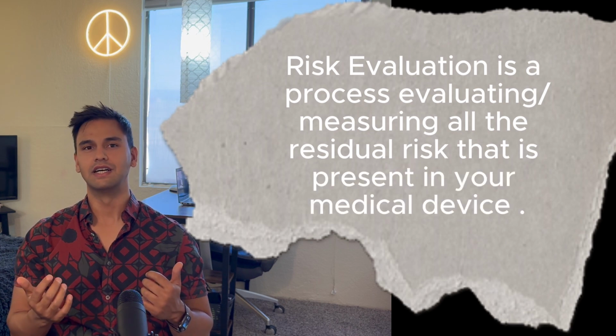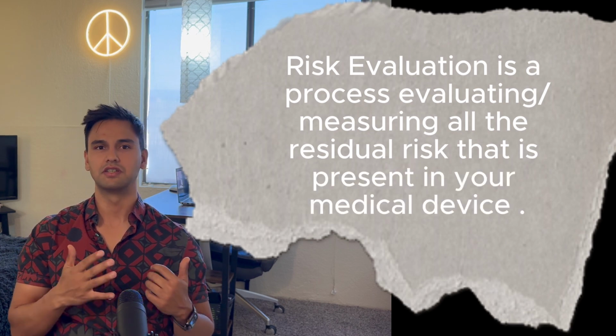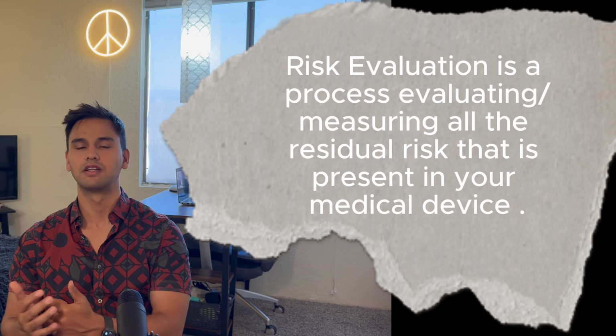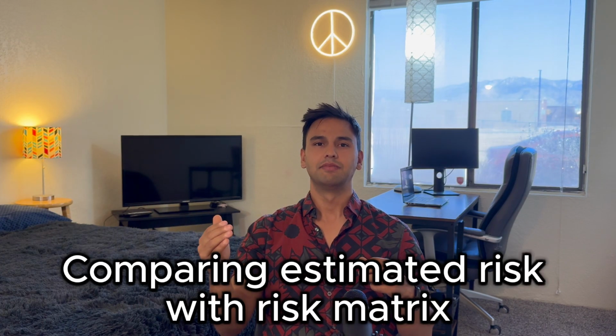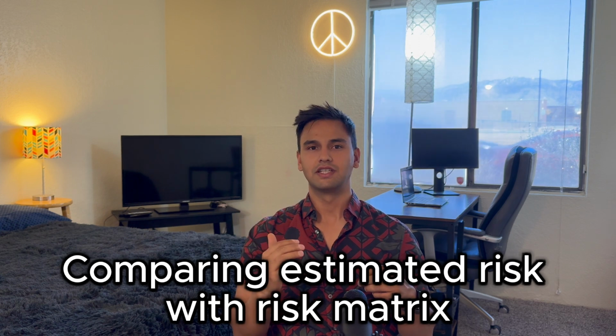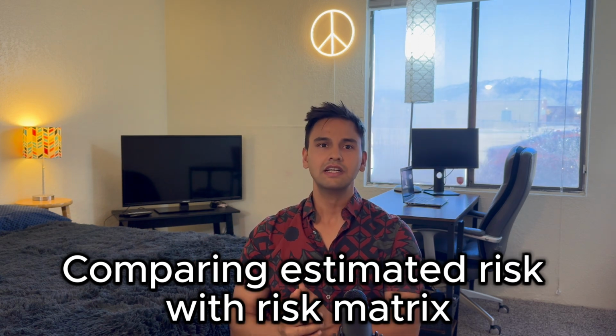So risk evaluation: once the risks associated with a medical device have been identified, they need to be evaluated to determine whether they're acceptable or not, right? This is done by comparing the estimated risk with the pre-established criteria for risk acceptability. This criteria should be based on your company's risk acceptability policy as well as applicable regulations and standards.